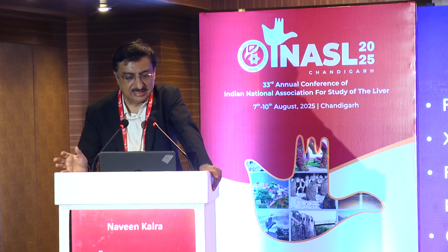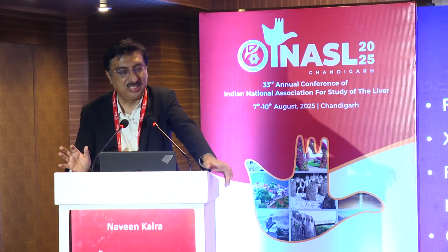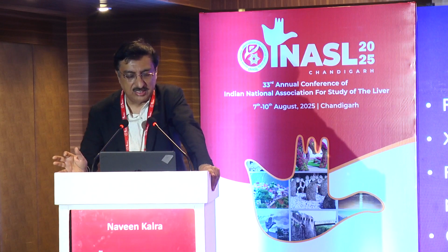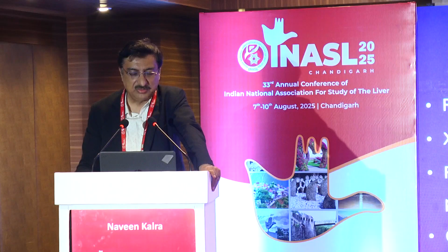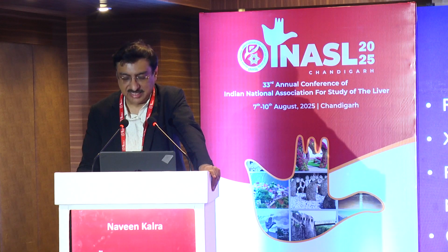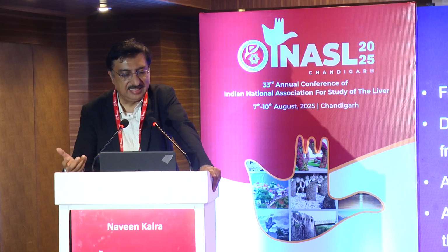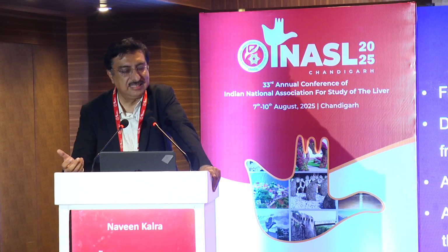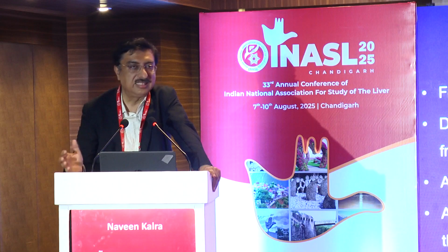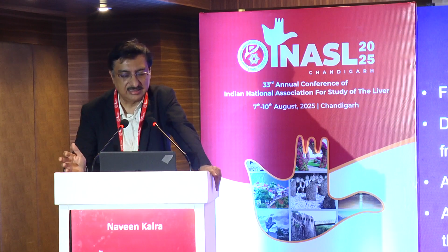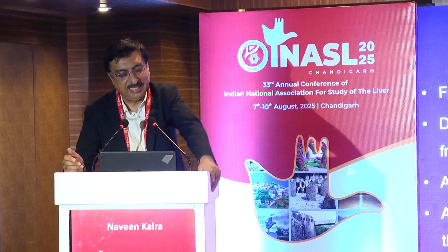And this is over the right lobe of the liver. Sometimes you can place it on the right lateral abdominal wall, and then you hold it in place with an elastic strap under the phased array coil. The driver sends in acoustic vibrations at 60 hertz, and you can set the amplitude, which is usually 50%. If the patient is obese, you spike up the amplitude.